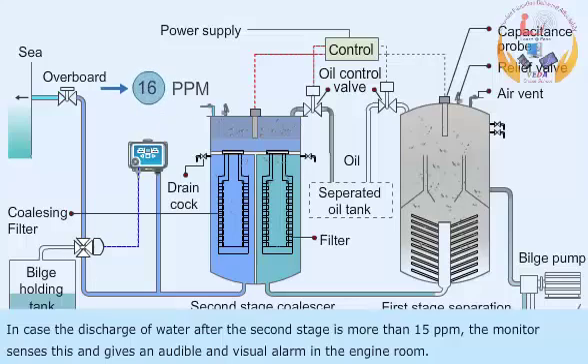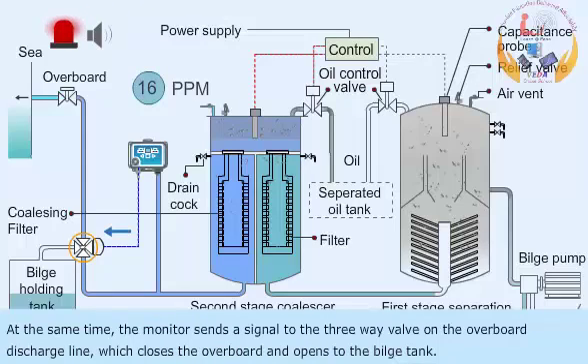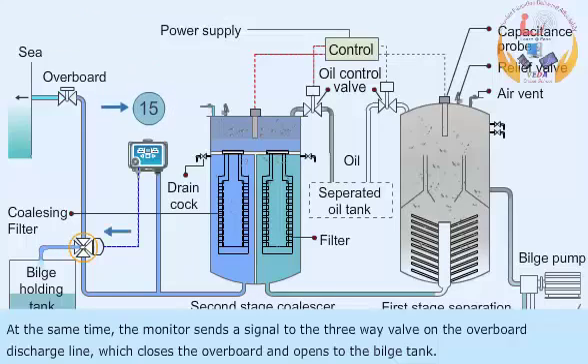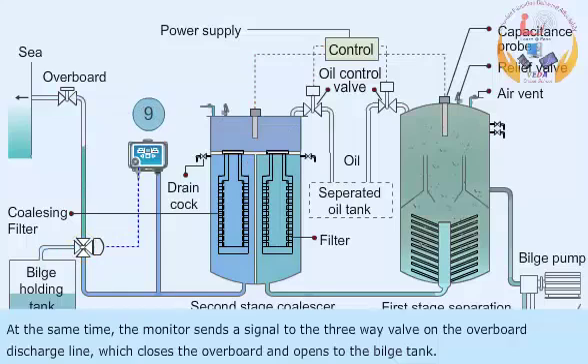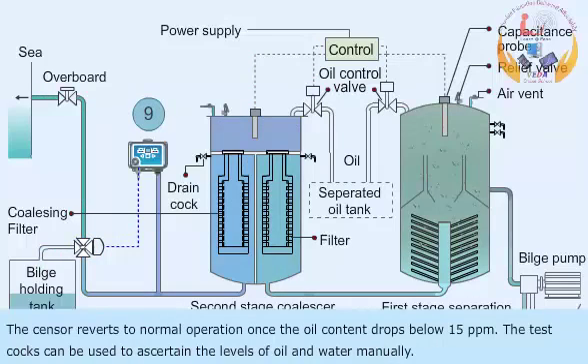Oil content of the final discharge is below 15 ppm. In case the discharge of water after the second stage is more than 15 ppm, the monitor senses this and gives an audible and visual alarm in the engine room. At the same time, the monitor sends a signal to the three-way valve on the overboard discharge line, which closes the overboard and opens to the bilge tank. The sensor reverts to normal operation once the oil content drops below 15 ppm.